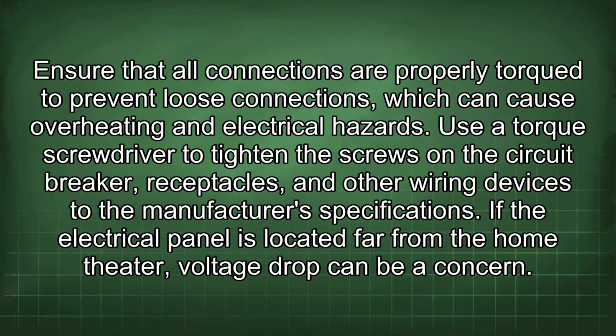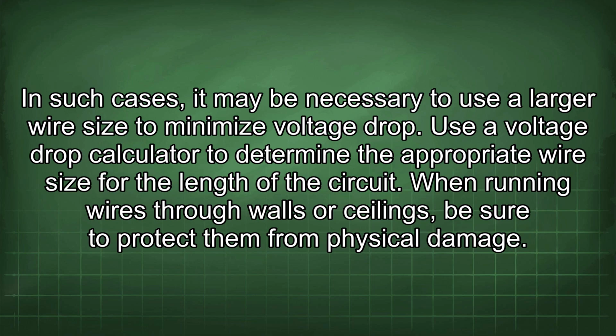Ensure that all connections are properly torqued to prevent loose connections, which can cause overheating and electrical hazards. Use a torque screwdriver to tighten the screws on the circuit breaker, receptacles, and other wiring devices to the manufacturer's specifications. If the electrical panel is located far from the home theater, voltage drop can be a concern. In such cases, it may be necessary to use a larger wire size to minimize voltage drop. Use a voltage drop calculator to determine the appropriate wire size for the length of the circuit.